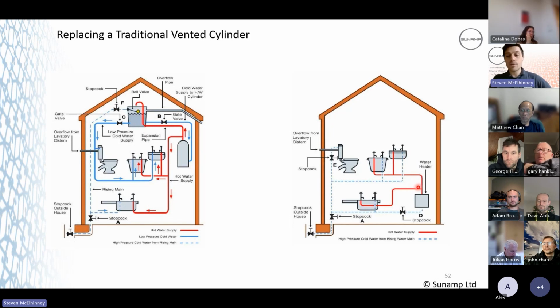When we talk about the blending valve, we advise having that blending valve fitted as close as you can to the battery. We've had some jobs where the specification engineers haven't specified a blending valve at the battery, and they've relied on the TMV below the bath and below the sink in the bathroom. That's great for the bath and the sink in the bathroom, but there's nothing downstairs. So you've got that raw thermal energy coming at your downstairs toilet tap and the kitchen tap, basically depleting the battery faster. But also if you're running the bath or the sink up here, you've got your blending valves, that's brilliant, but again, you've got that pipework filled with that raw thermal energy from the battery, unblended. So it just creates capacity issues for the customer.